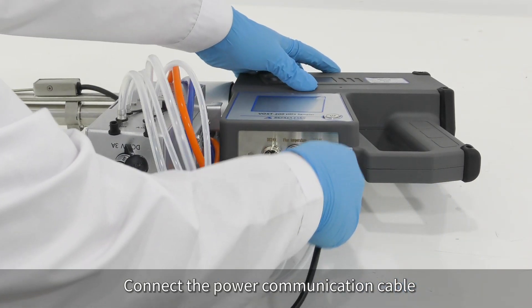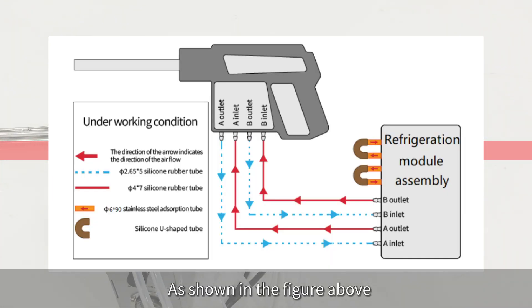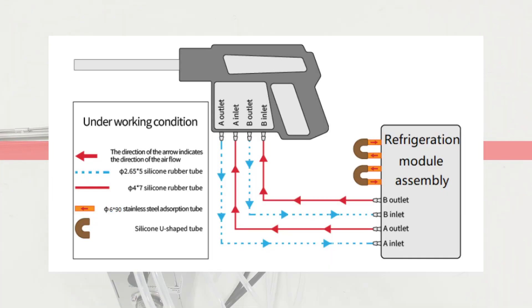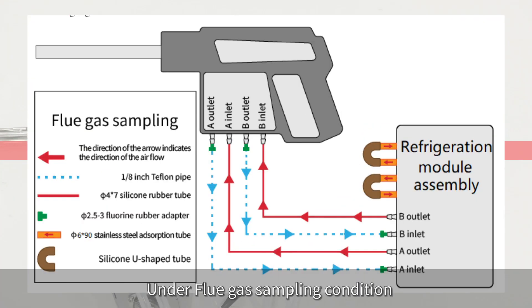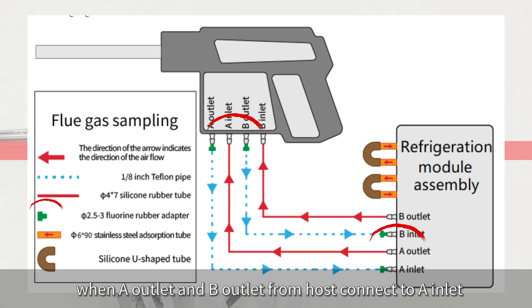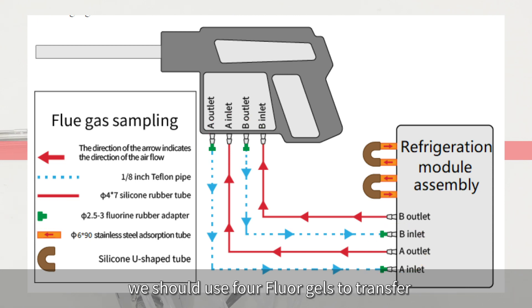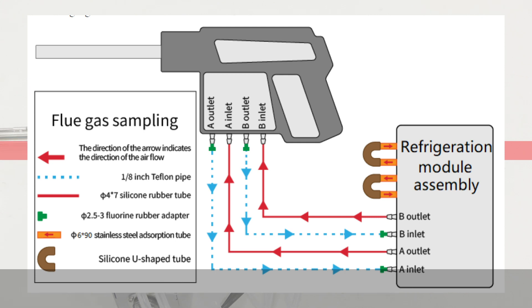Connect the power communication cable. Under flue gas sampling condition, there is only one difference: when connecting A-outlet and B-outlet from the host to A-inlet and B-inlet of the refrigeration module, you should use four fluor gel transfer sleeves. Everything else remains the same as before.